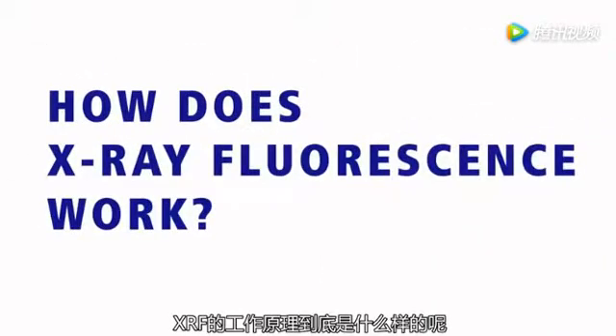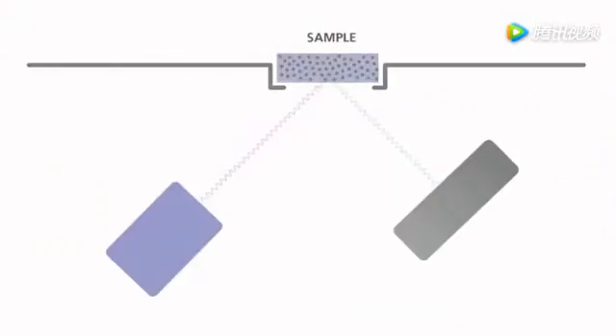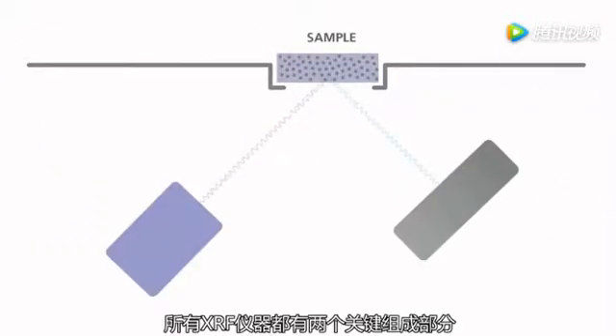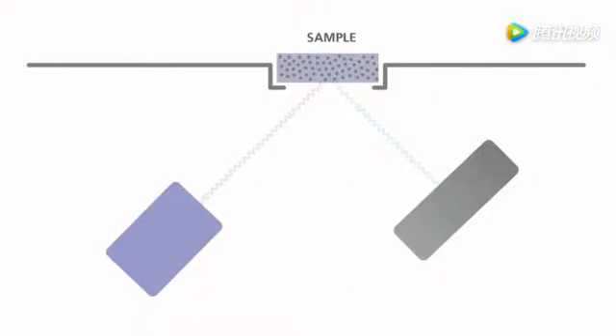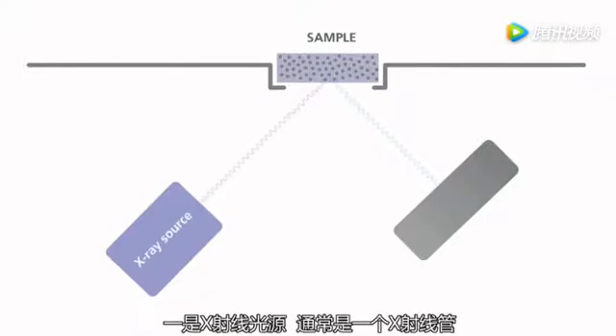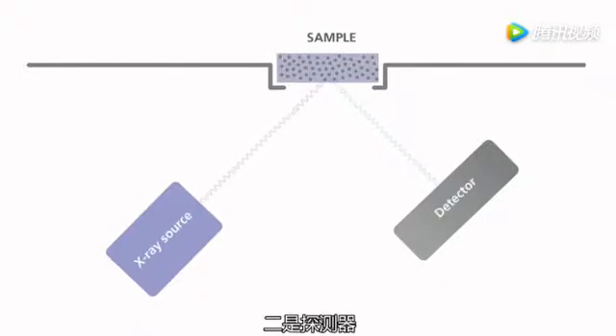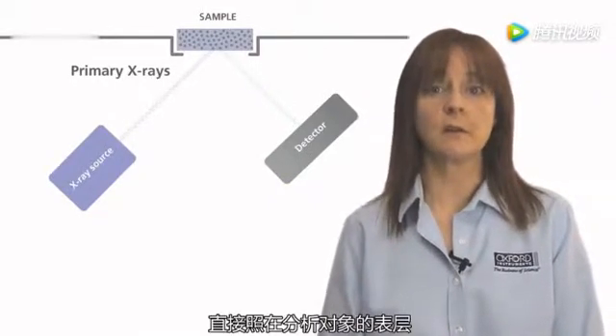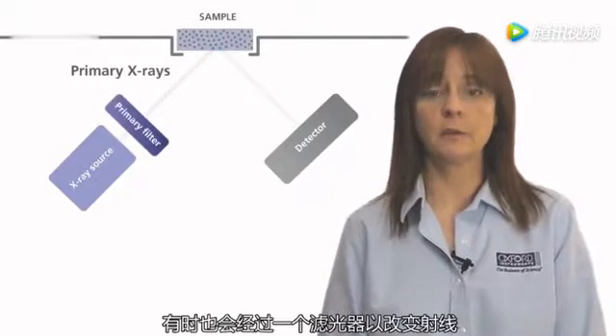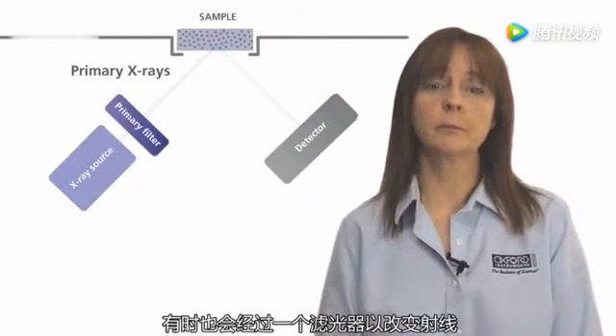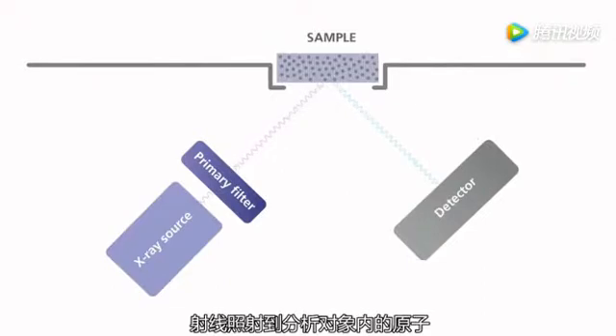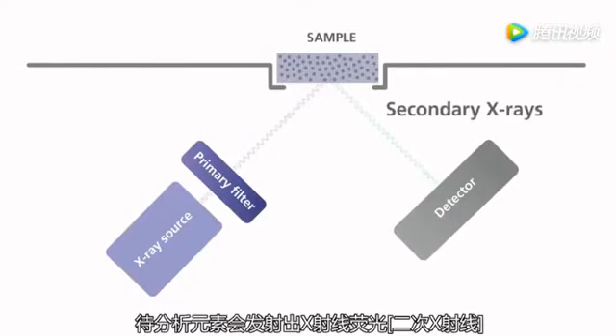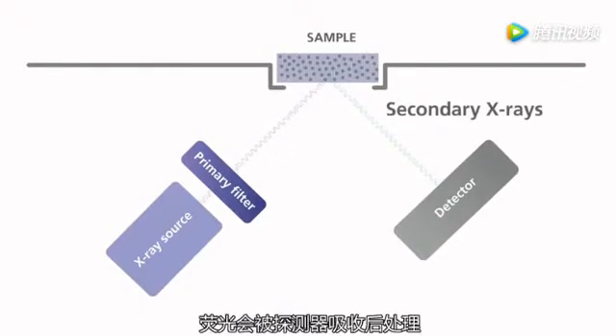So, how does X-ray fluorescence work? All XRF instruments are designed around two major components: an X-ray source, commonly an X-ray tube, and a detector. Primary X-rays are generated by the source and directed at the sample's surface, sometimes passing through a filter to modify the X-ray beam. When the beam hits the atoms in the sample, they react by generating secondary X-rays that are collected and processed by a detector.